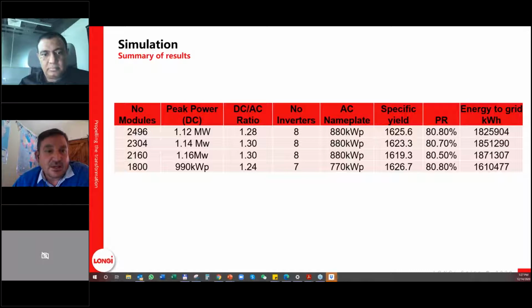The next thing I looked at was the HIMO 5, the 70 cell half cell module, with a power of 535 watt peak. Out of that, we get 1.16 megawatts, about 200 kilowatts more than the 450 watt module, still 1.3 in terms of DC to AC ratio. But what was interesting is that compared to the other two modules, the specific yield is down by quite a bit in comparison. I found that quite interesting.